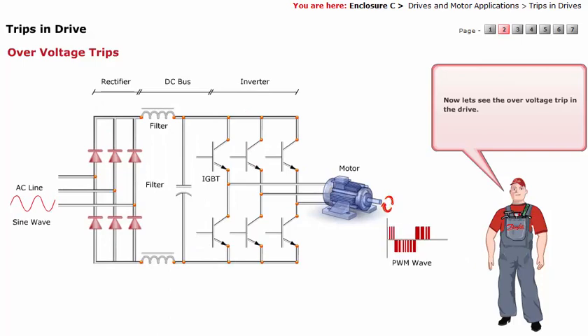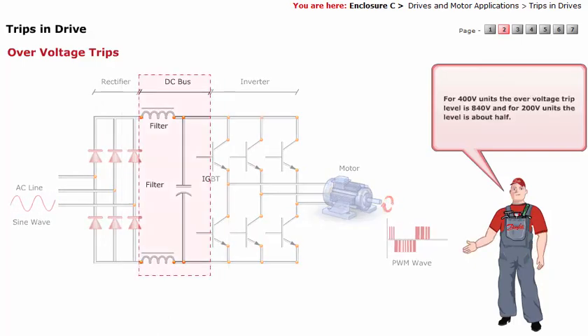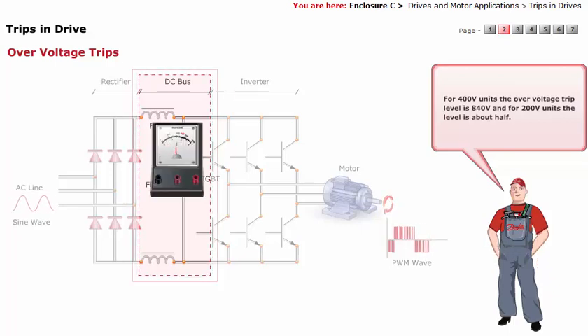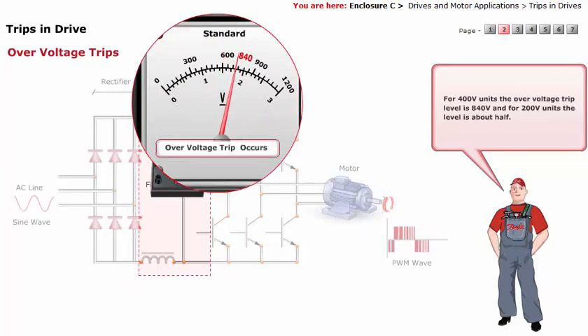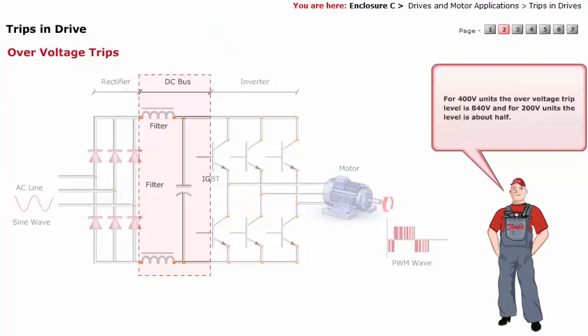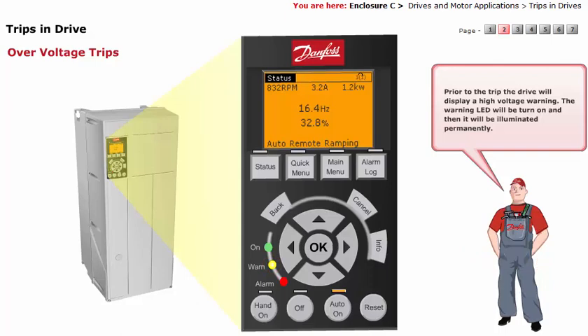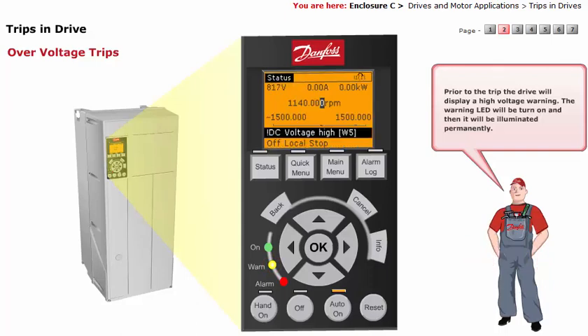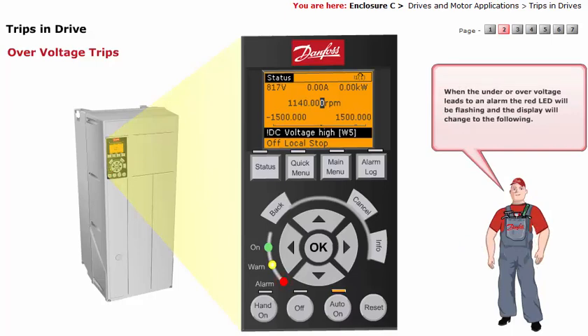Now let's see the over voltage trip in the drive. For 400 volt units, the over voltage trip level is 840 volts, and for 200 volt units the level is about half. Prior to the trip, the drive will display a high voltage warning. The warning LED will be turned on and then illuminated permanently. When the under or over voltage leads to an alarm, the red LED will be flashing and the display will change accordingly.